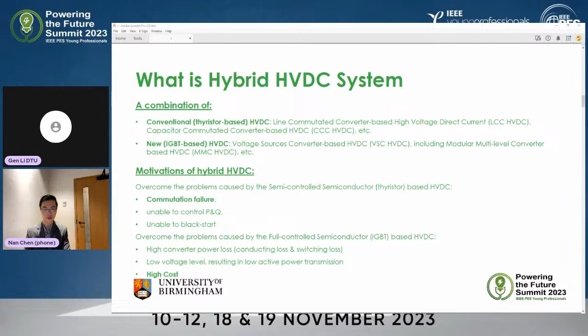So the motivations for proposing the hybrid form of HVDC: firstly, we would like to overcome problems caused by the semi-controlled semiconductor, thyristor-based HVDC. First, commutation failure. Second, inability to control active power and reactive power independently. Third, inability to black start. The second aspect is to overcome problems caused by full controlled semiconductor-based HVDC. First, high converter power loss, including conducting loss and switching loss. Second, low voltage level, resulting in low active power transmission. Third, high cost. Next page, please.